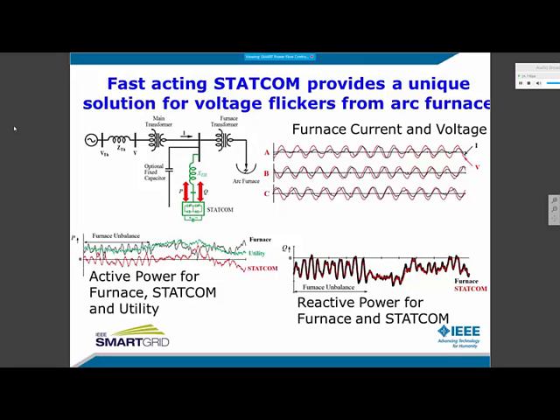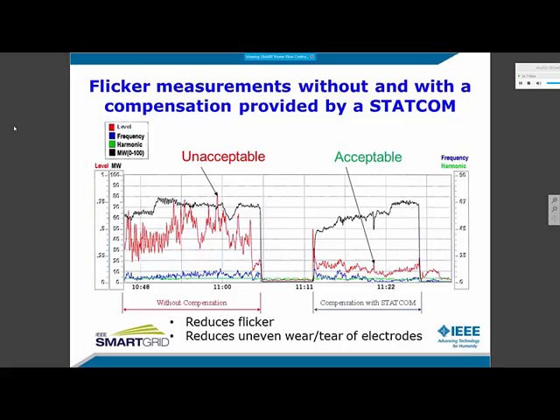In addition, the STATCOM can do more. It can be operated to exchange net zero active power, as shown by the red line, to smooth out the power demand from the utility. Now, the result is remarkable. As you see, the STATCOM not only reduces the flicker to an acceptable level, as shown in this red line, it also reduces the wear and tear of the electrodes, resulting in greater savings.